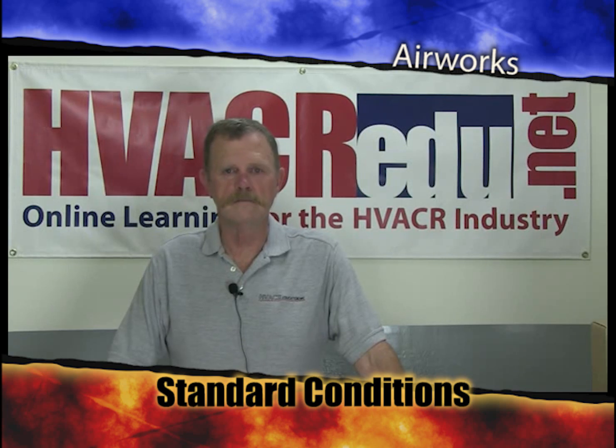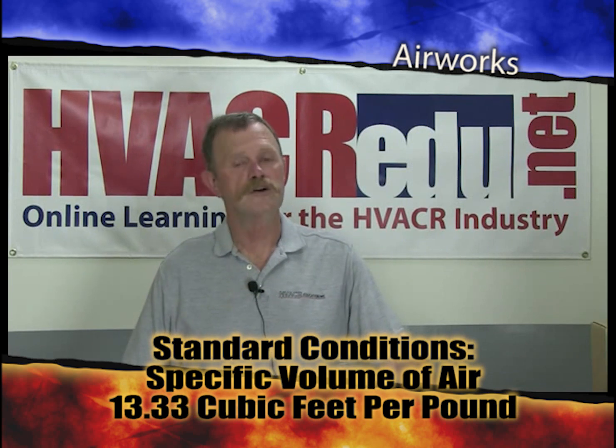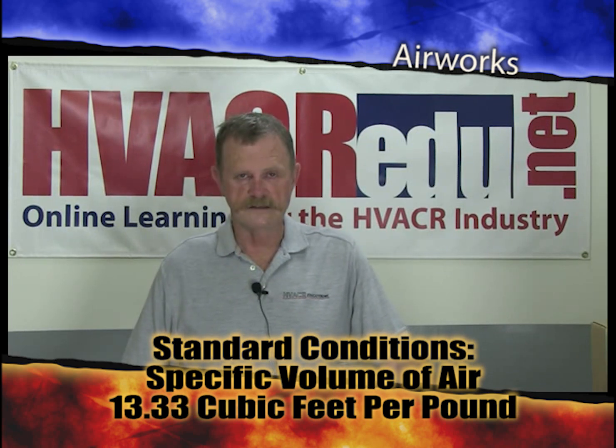One of the issues about air in HVAC is what is called standard conditions. And obviously, we need something to measure from. So in the HVAC world, that measurement platform is called standard conditions. So what does standard conditions mean? Standard conditions mean the specific volume of air is 13.33 cubic feet per pound. That is a specific volume of air under standard conditions.